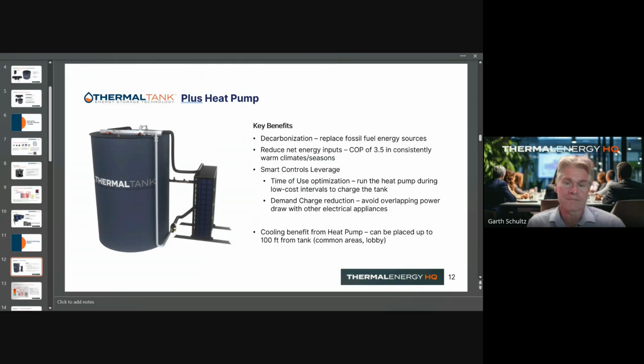Right, and so the art is really in the sizing—figuring out what the demands are over the course of the day, even over the course of the year, and when the peak demands occur. Then pairing that with the rate cycle. So if you could run the heat pump all night long at a very low cost, you do need enough thermal storage capacity to put that heat somewhere, right? If you have a small tank, the heat pump will simply heat it up and then it's done. And if that water gets used in the morning, the heat pump has to run again during a high-cost rate cycle. So that's the dynamic we're looking for here.